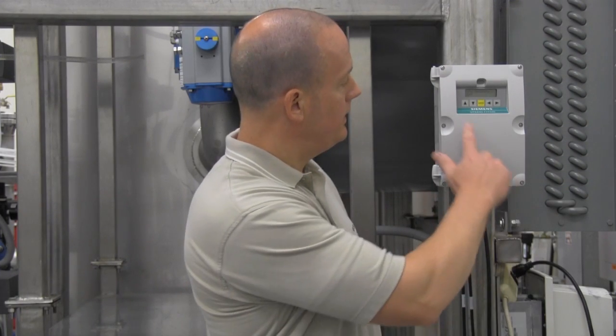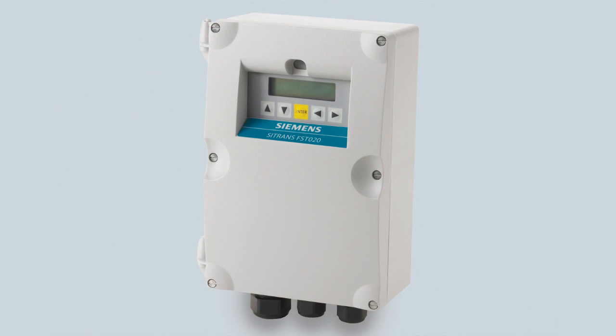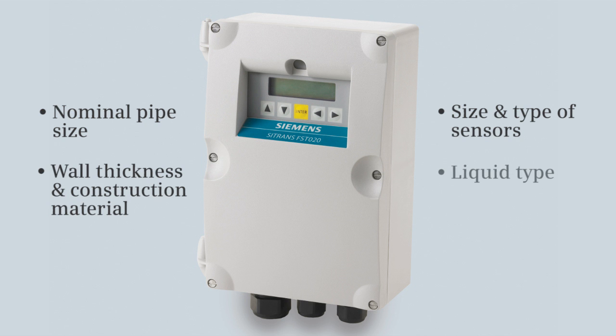For this exercise, we will program the meter using the keypad. So let's start the demonstration. To configure the FST020, we need the following application details: the nominal pipe size, wall thickness and construction material at the sensor location, the size and type of sensors we will be using, and the type of liquid we will be measuring. We only need to set four parameters to start measuring flow.